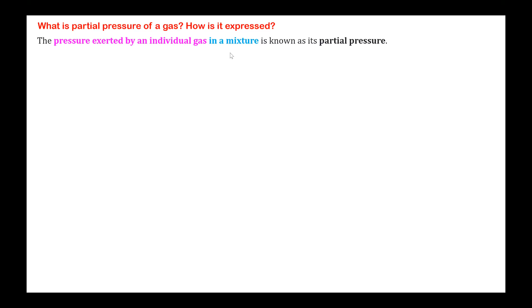It is usually reported as percentage or fraction of the delivered gas mixture. For example, where it will be 1 atmospheric pressure. Even though we deliver gases and vapors from the anesthesia machine, ultimately it is delivered at atmospheric pressure. Even though you have a cylinder pressure of 2000 psi for oxygen, it is reduced at various levels.